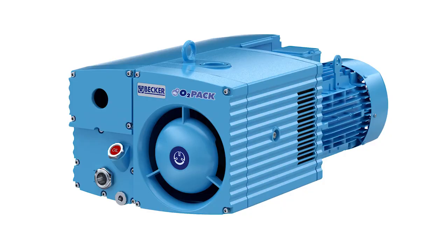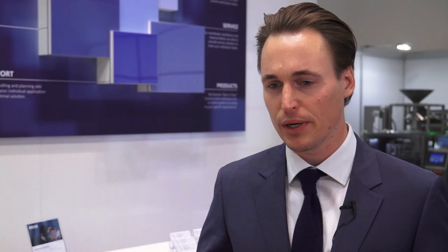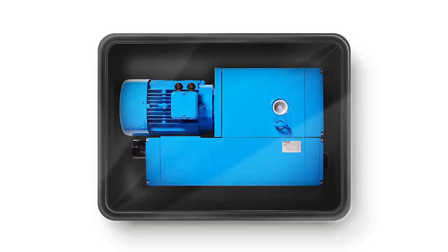We have a special version of the U5 oil-lubricated rotary vane vacuum pump which we call the O2PACK — a pump especially designed for oxygen pumping. Whenever you talk about packaging red meat products, you usually use oxygen. It's pretty unique because the construction dimensions don't grow. Solutions on the market usually need a three-stage separation process for the oil; we also have these three stages of separation, but instead of adding them externally, we've integrated them inside the pump.